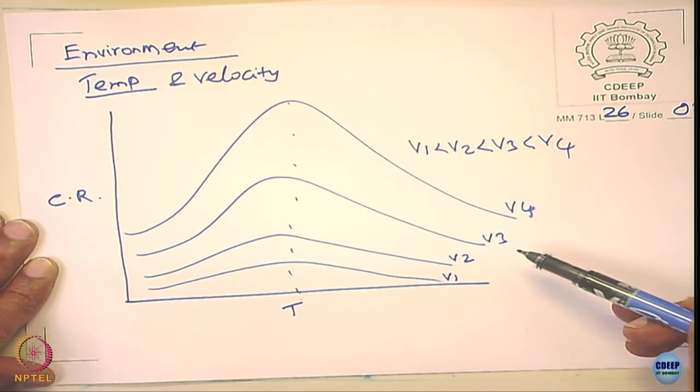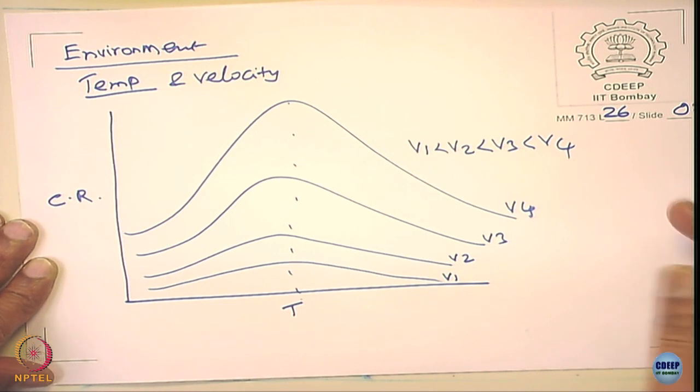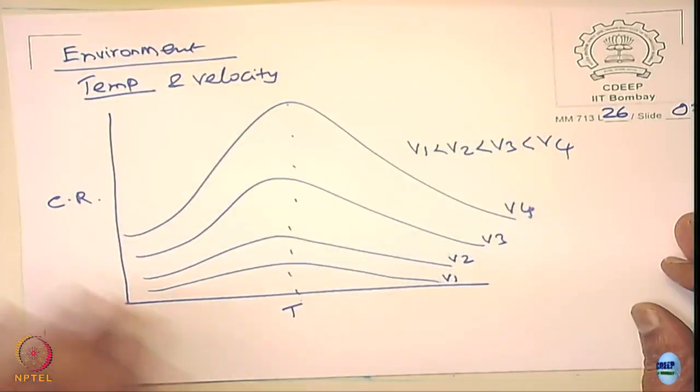It is not same as we discussed earlier, you remember earlier we discussed the effect of temperature on the corrosion rate of water. Remember, I said that when you rise the temperature above 85 or so, the corrosion rate of water drops because the oxygen escapes from the surface, right, from the water. In a boiler, that does not happen, right. The oxygen cannot escape from that, nor is oxygen present in this water at all.